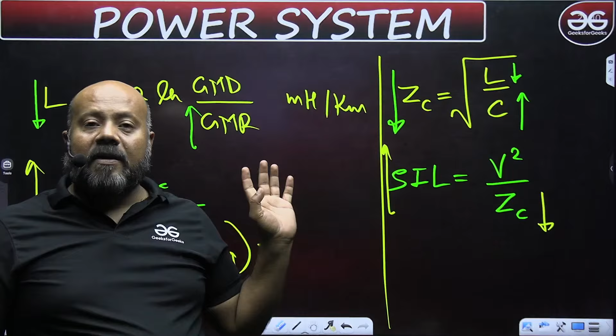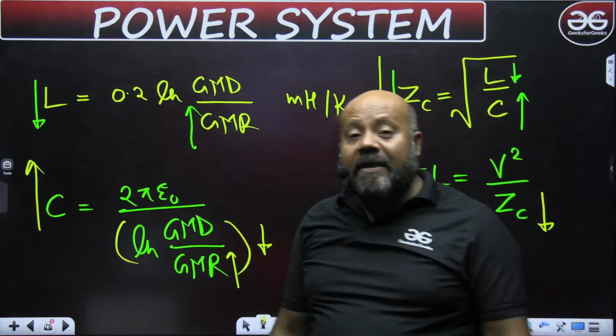As you are saying, is it physical radius? No, it's not physical radius. I will tell you, I will prove it. You can say it is physical radius only if it is a single conductor. If it is any other conductor, if it is stranded, if it is bundled, you cannot say this. The GMR in case of capacitance is the GMR as you calculate for inductance, but without the factor 0.7788. Rest everything is exactly the same. I hope you are getting this.